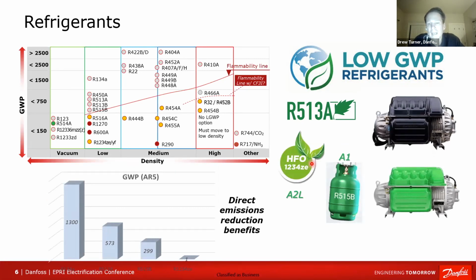And with refrigerants, the point that we make, and this ties back to the dynamic compression, is that as you go low GWP and minimize flammability, that in turn pushes you down the density line. And I'm sure Loic is going to talk about this as well, but to get to minimized GWP while at the same time minimizing the flammability risk, that in turn drives you to technology that is optimized for moving a high volume of lower pressure refrigerant, as opposed to squeezing a lower volume of high pressure refrigerant. And that in turn, of course, drives you towards dynamic compression. So it all ties back together.